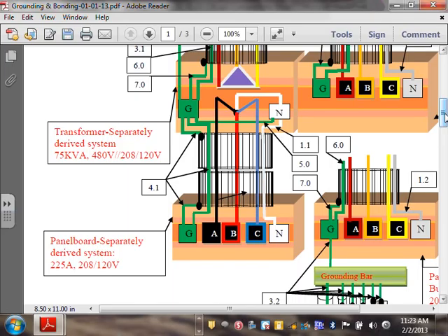Okay, so we got these guys. We got that number 2 here. Any comments? Any questions about the number 5, which is the system bonding jumper? System bonding jumper. Now there are two things I want to pinpoint. Now from the transformer into the panel, you also have to have a neutral. Can you guys see that white conductor, the neutral conductor?